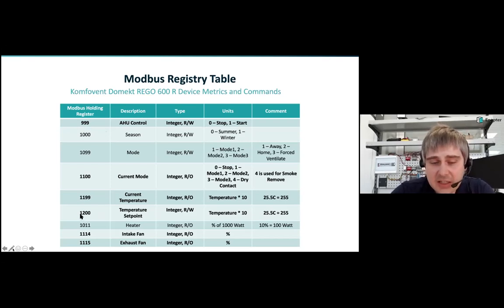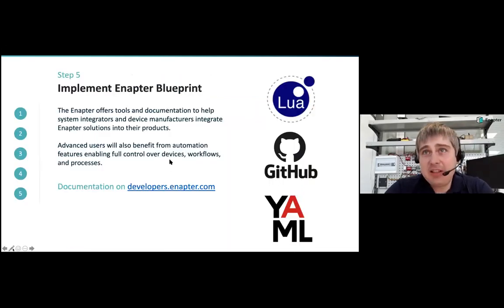In the register 1200, there is a temperature set point, and this is a read-write register. But what is important, the temperature there is stored multiplied by 10. So, for example, if we would like to set 25.5 Celsius, in this case, we need to set 255 into this register. For all other registers, the principles are the same, so there is no need to explain all of them. Let's go to the next step. The next step is the last one.